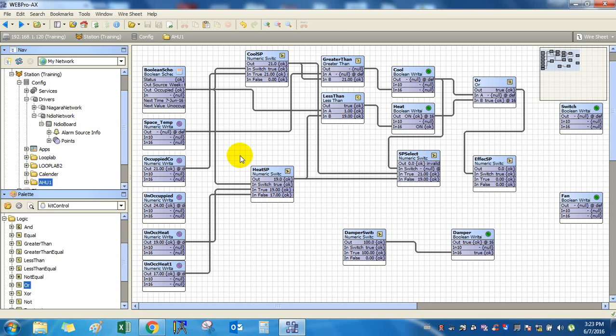Then you have lots of things. Economizer mode is there. You might have modulating cooling, modulating heating. Then you might have 2-stage heating, 3-stage heating. Or you might have a modulating damper controlling your carbon dioxide, CO2 control, and things like that. So this is just the basic one. About AHU and chiller, the chiller is the difficult one.